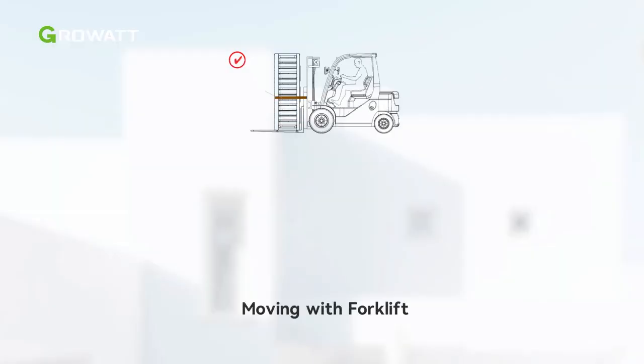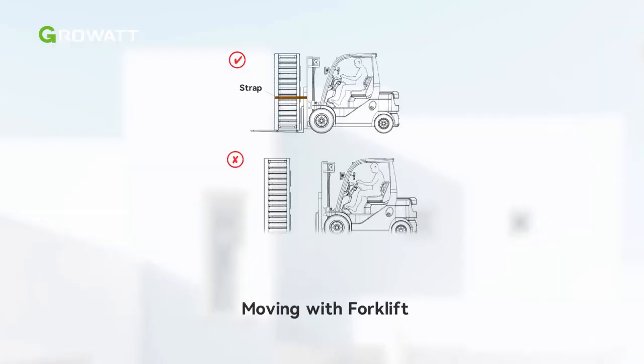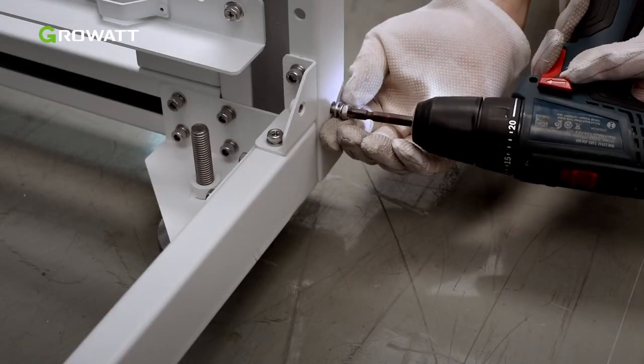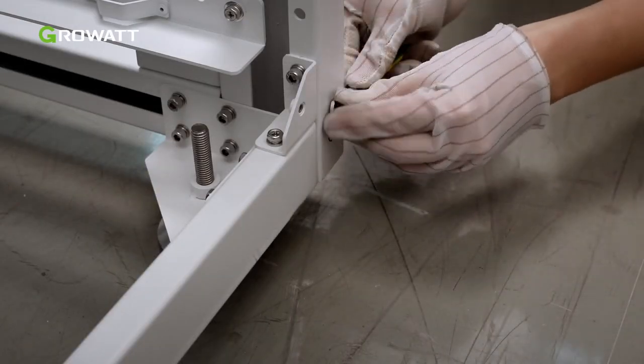When moving the equipment with a forklift, secure it properly according to the actual situation to avoid tip-overs. Do not transport racks with batteries. Ground the rack before installing the battery and high-voltage box.